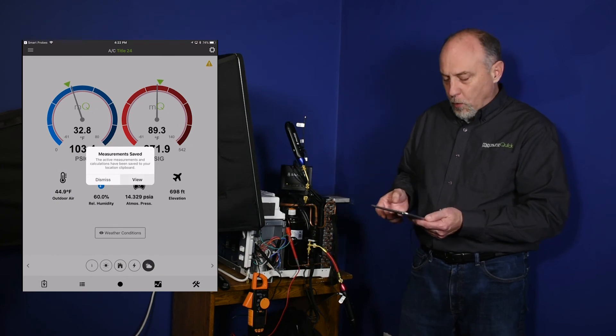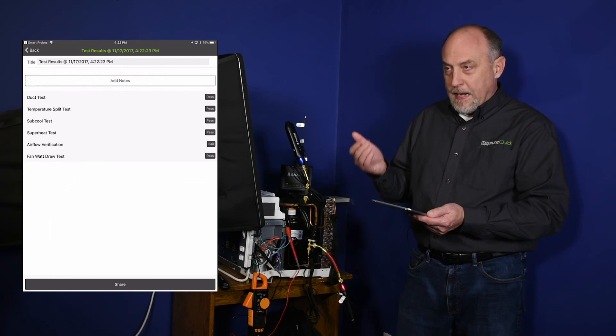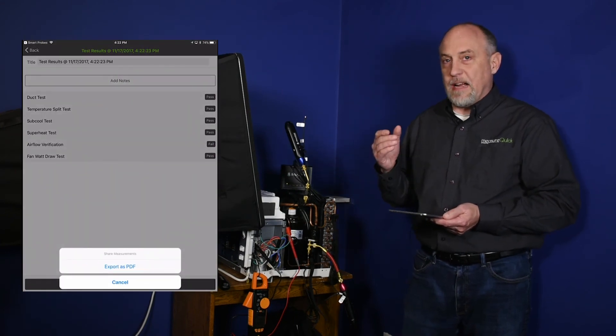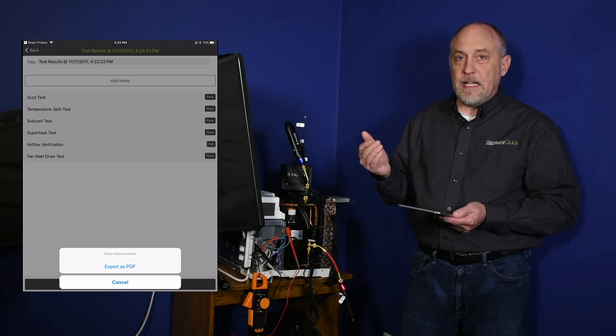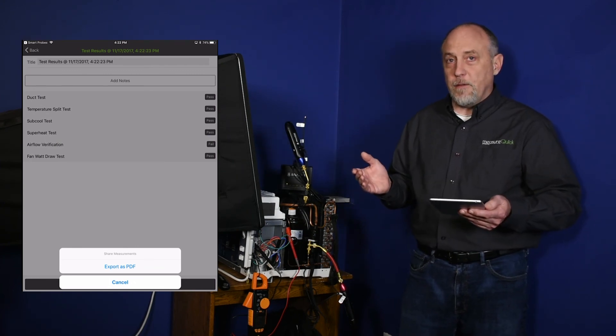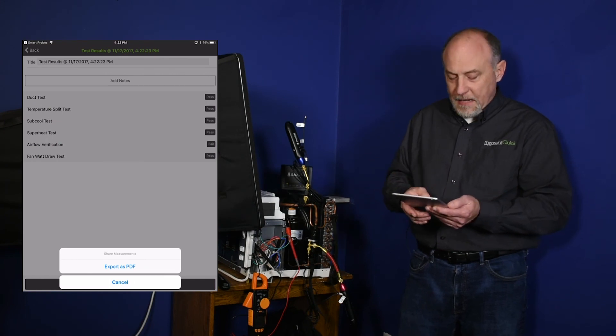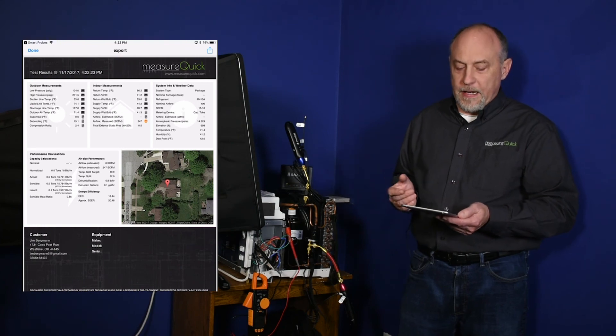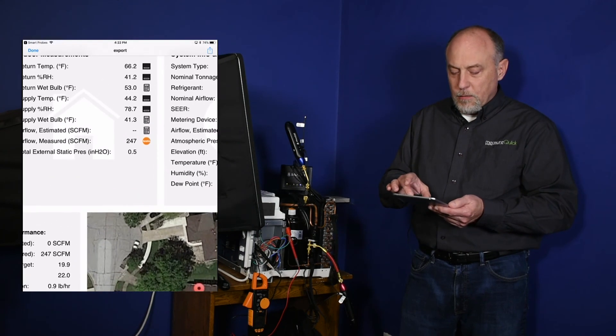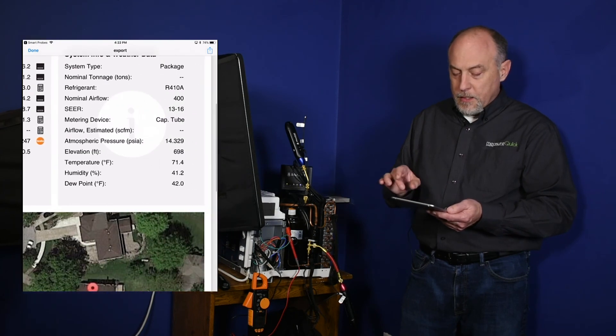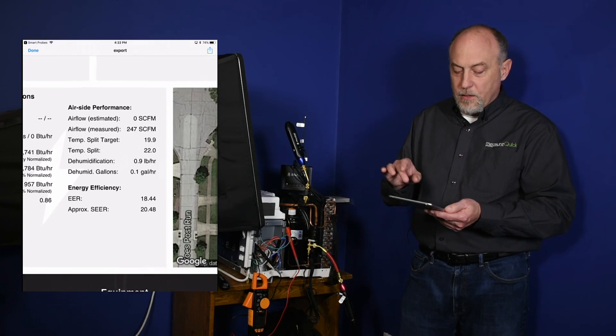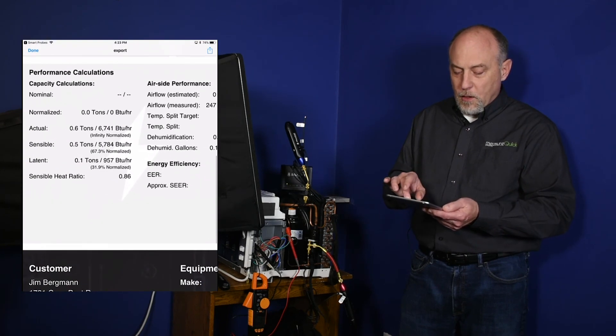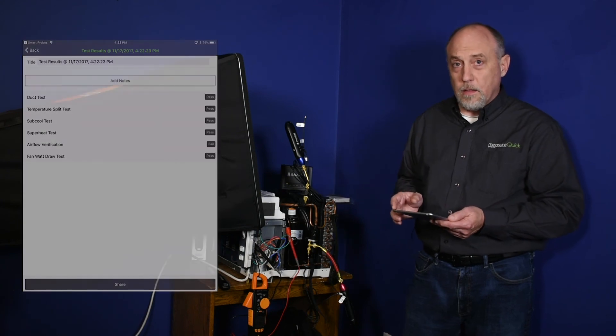And at this point here, I can share this data. Now in a couple days here, we're going to have this set up so it automatically goes out to the registry and populates that data. So we are literally pass, fail in the field right now. All this data can be done that fast. We hit export PDF and there's your report generated. All your readings, you can see we'll zoom in here on this Testo. The Testo was measured off the capture hood. You can see all the calculated values with a little calculator, all the iConnect values, our estimated airflows, our BTUs. All that information in, done, and ready to go.